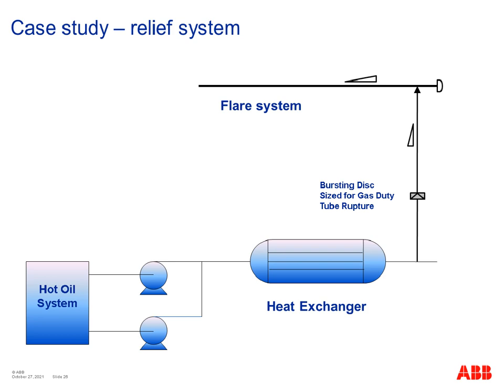So another case study. In this one, we have a hot oil system going through the tubes of a heat exchanger, and it's coming from 2 pumps. We've got a duty pump and a standby pump, and it's sending material off to another hot oil tank. On the shell side, we have the process stream, which is a gas, and on the tube side, downstream of the exchanger, we have a bursting disc sending material into a flare system. And that bursting disc is designed for a gas duty, so breakthrough of the process gas in the event of tube failure in the exchanger. So that's what that bursting disc is sized for.